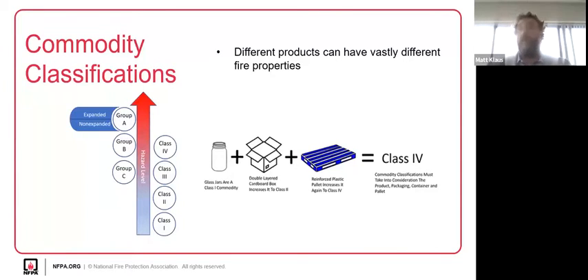Maybe inherently, my building and area have a great water supply and it doesn't impact me much. Maybe it means I need to put in a fire pump. Going from Class 1 or 2 and changing the packaging, climbing that commodity ladder, and needing a lot more water can be a huge financial impact. So a lot of people design their buildings so that, say, the Group A plastics they sell are always on one side of the building with a really robust, expensive sprinkler system, rather than protecting the whole building for Group A plastics. We leave that stuff over here, but we have to make sure our operators aren't dragging Group A plastics into the Class 2 commodity protected space.